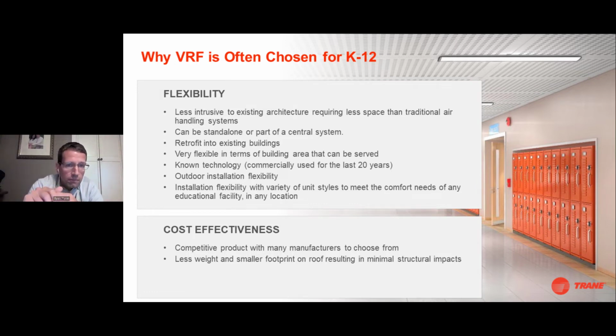Again, outdoor flexibility. We've seen these condensing units on roofs, at grade, and we've even seen them in basements of buildings, or in some cases, which we don't necessarily recommend, where people bracket them off of exterior walls. And also, these are just very flexible systems to meet the needs of almost any educational facility. Cost effectiveness. It's a competitive product with a lot of good manufacturers to choose from. These units are lighter with smaller footprints, resulting in a lot of the times minimal structural impacts in the building.